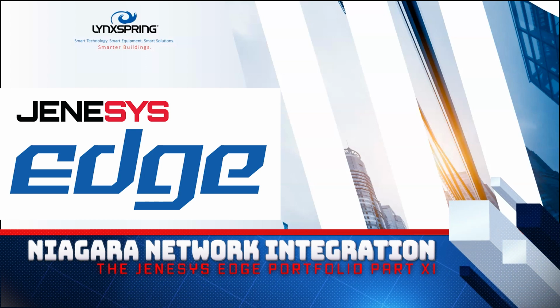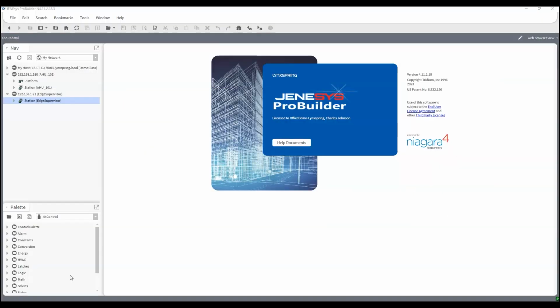Today we're going to be talking about Niagara network integration. Now, one of the purposes of a Niagara network is to model data originating from other Niagara stations. Proxy points under a Niagara station represent data received from other stations. Connections between stations function as client-server using the FOX protocol. The FOX protocol is also used for workbench to station communications.